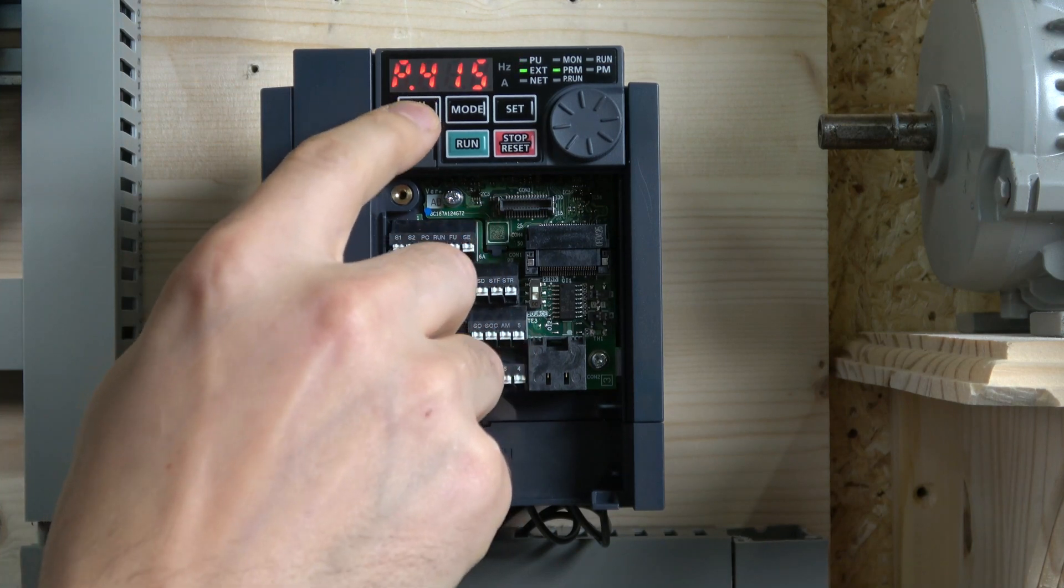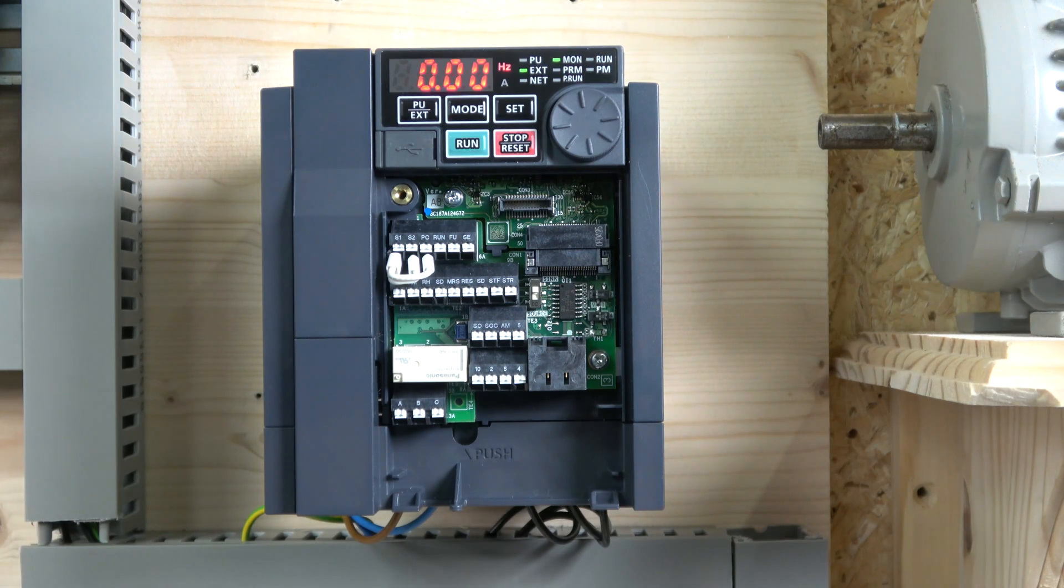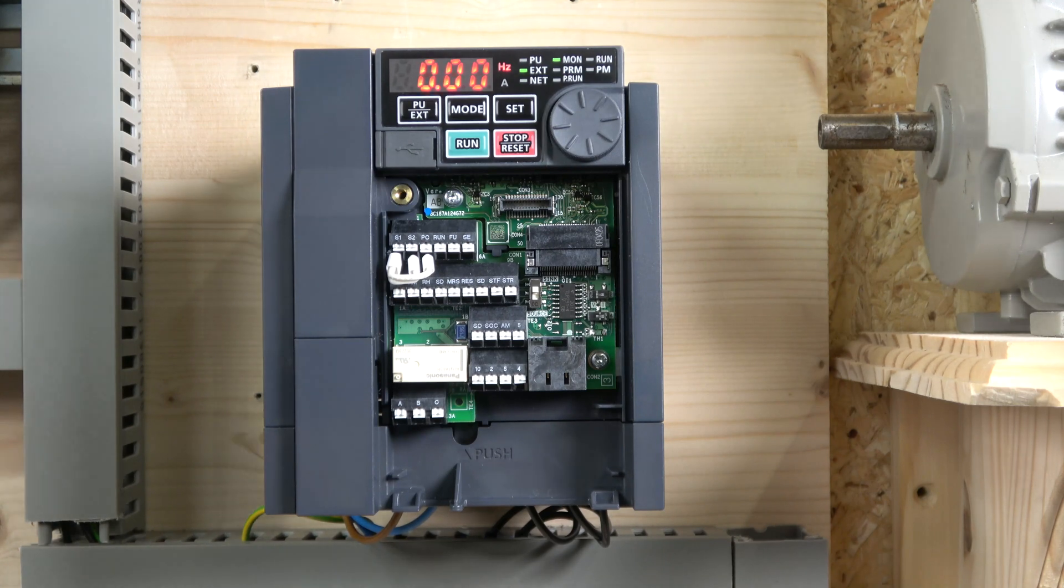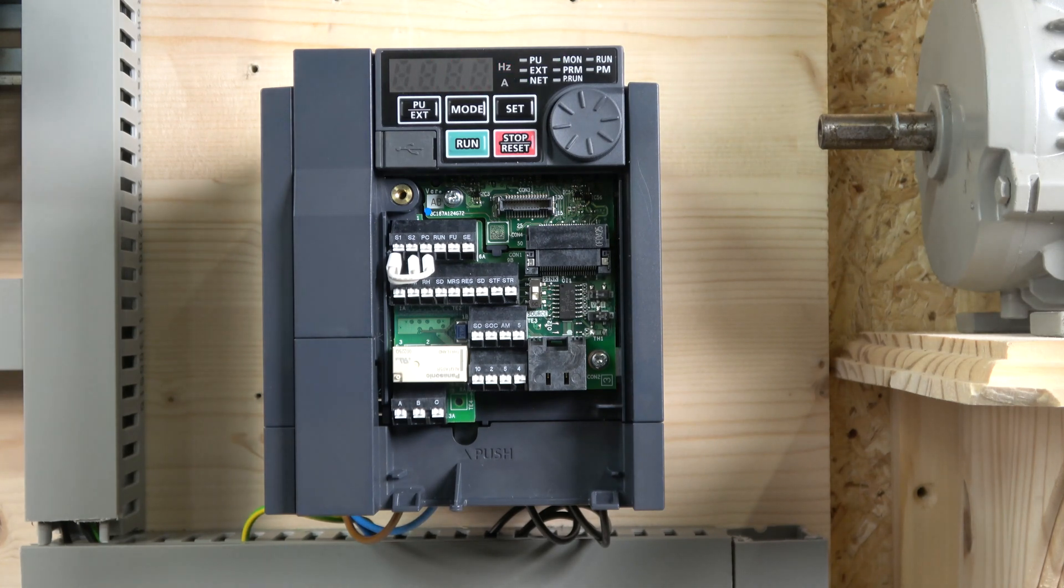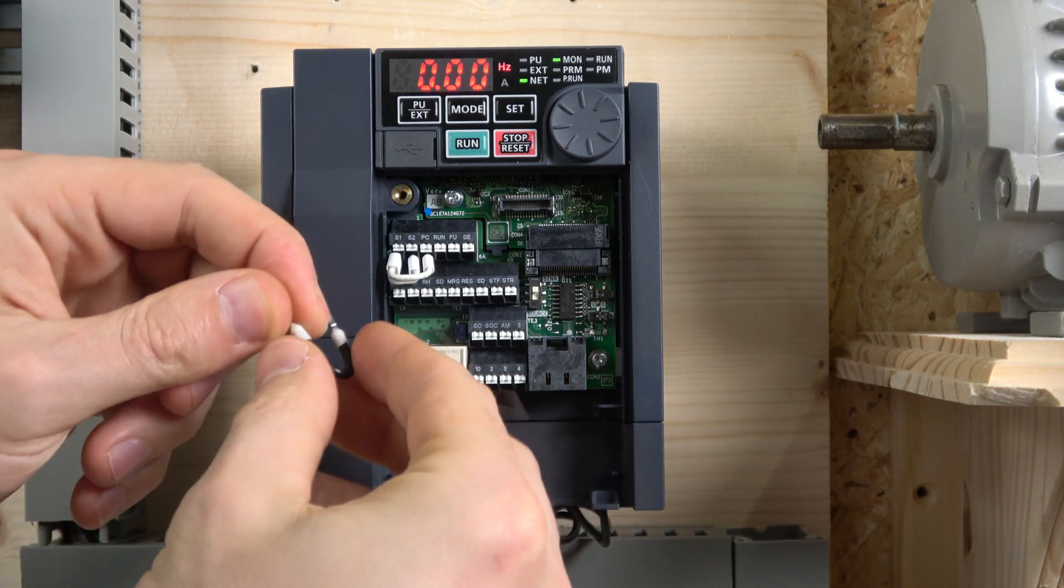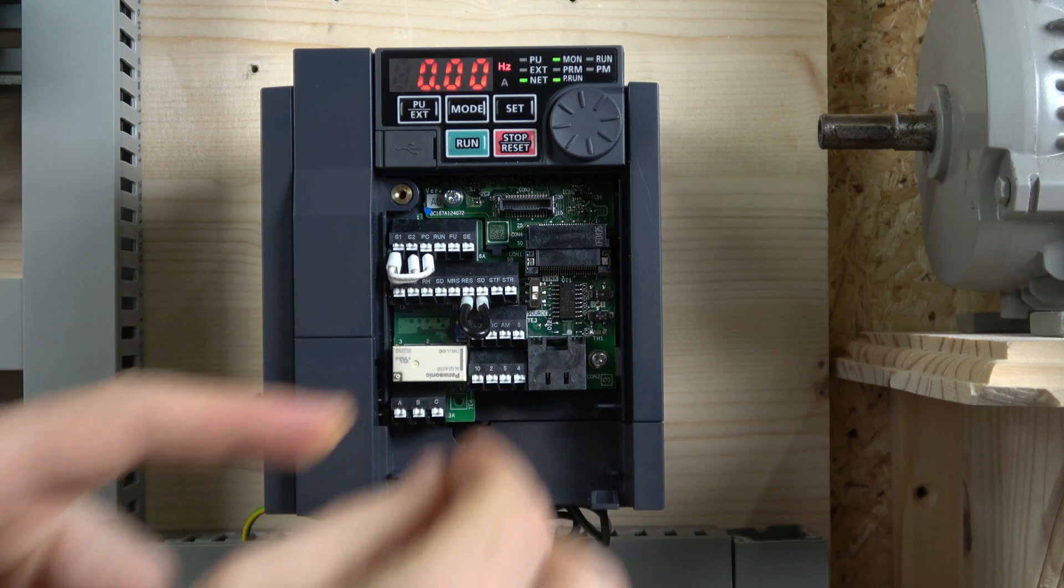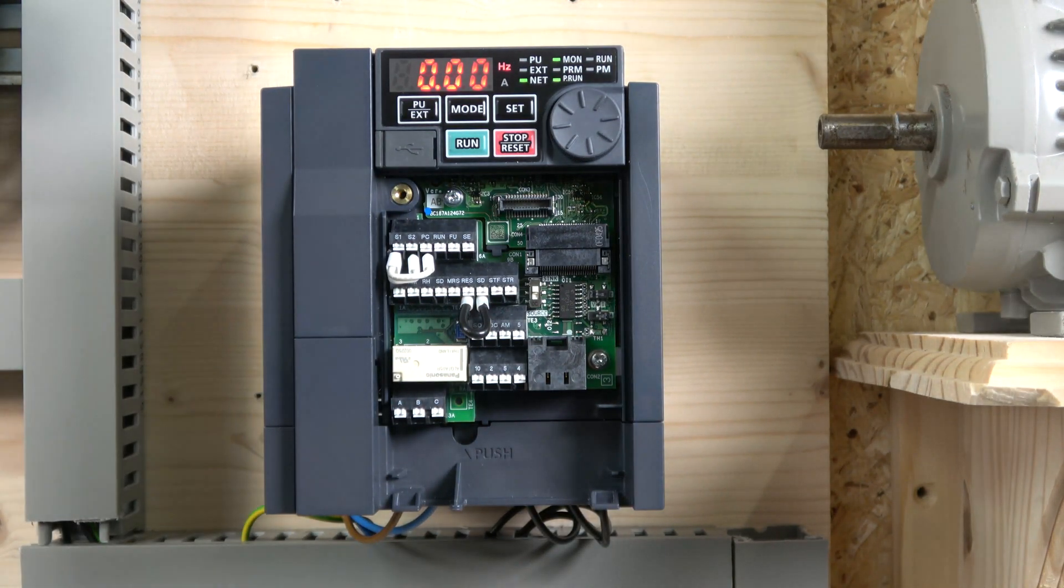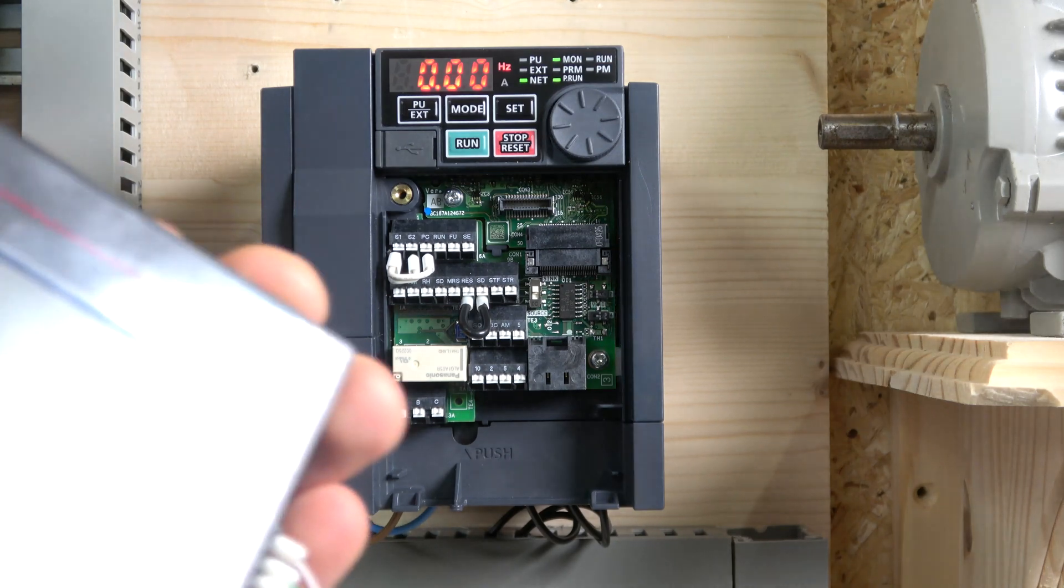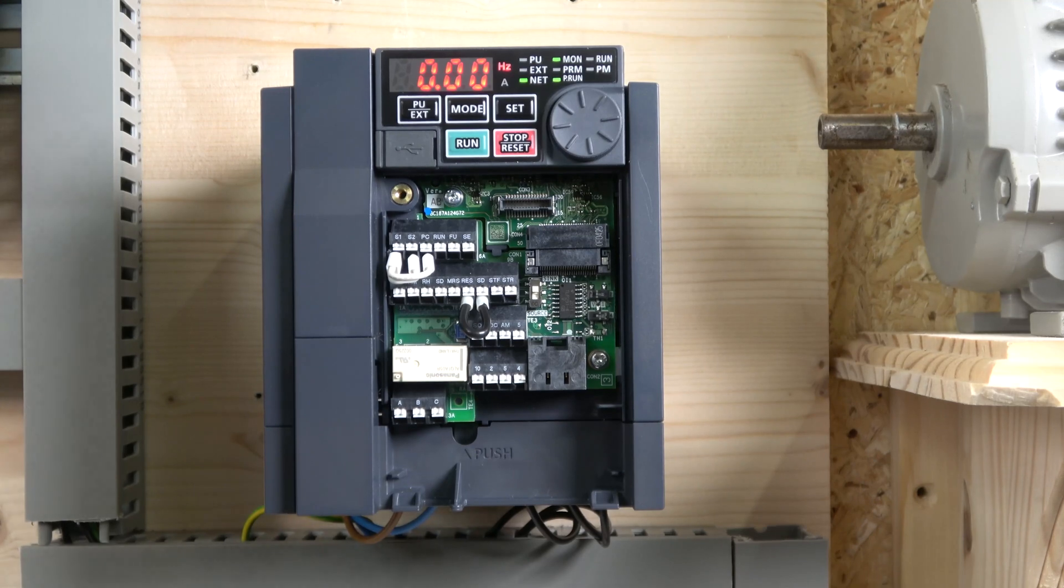Once you do that and reset the drive, it should go to net mode. As you can see, it jumped already to net. When you start back up, it will be in net. Next we need to activate our PLC functionality. As you can see, if you close these guys down, the PRUN comes on. If it doesn't come on, you've done something wrong. That's how you set your drive ready to work with your GOT. Let me wire up my GOT power and we'll go from there.